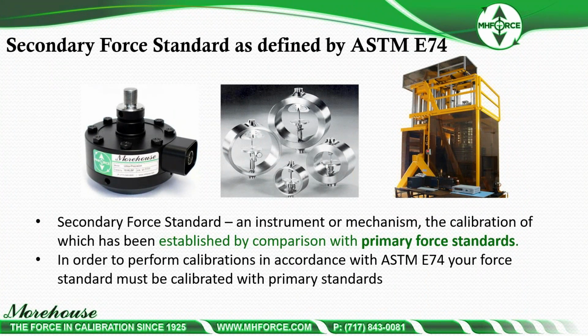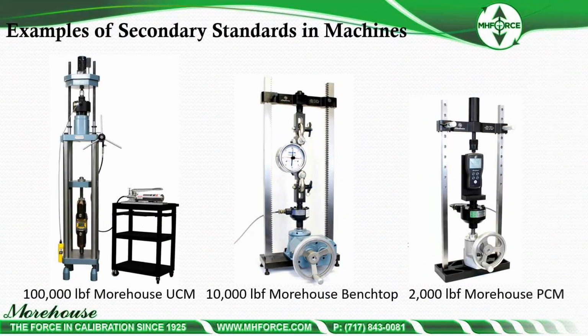Now, secondary force standard is pretty simple. An instrument or mechanism, the calibration of which has been established by comparison with primary standards. In order to perform calibrations in accordance with ASTM E74, your force standard must be calibrated with primary standards. People that are not getting their standards calibrated by primary standards cannot go out and assign another Class A loading range, which we will talk about later.